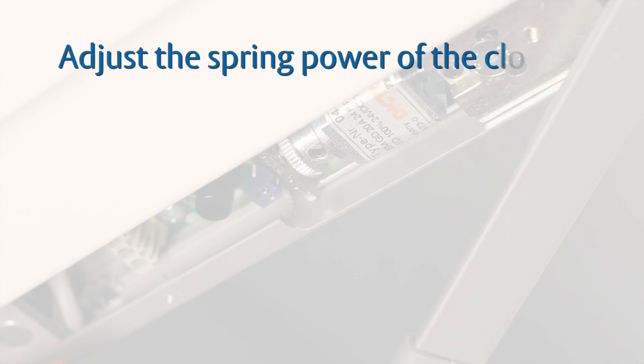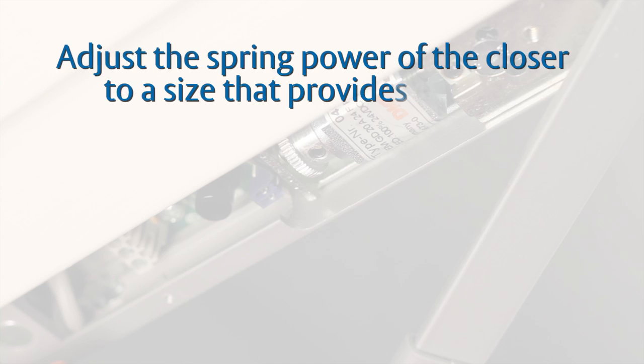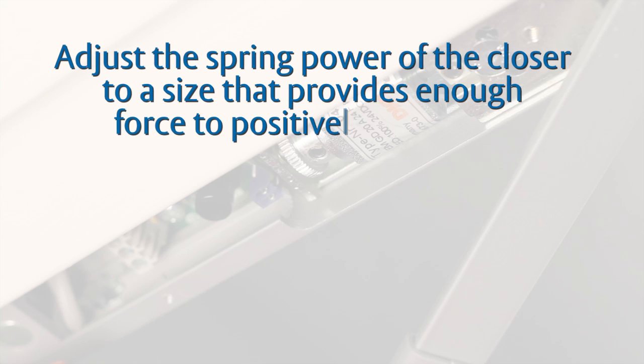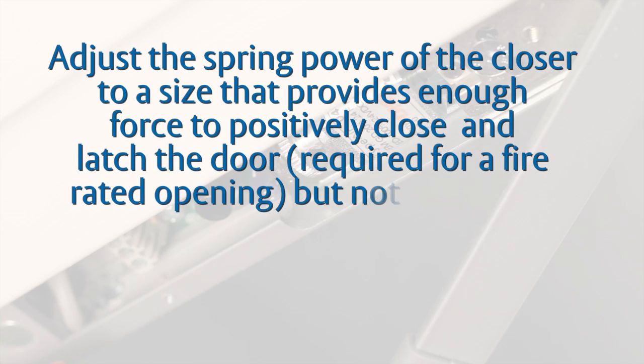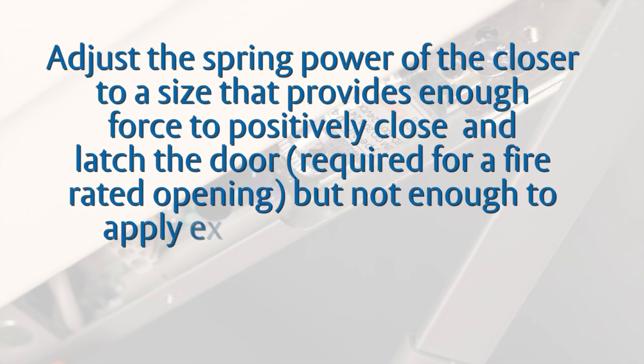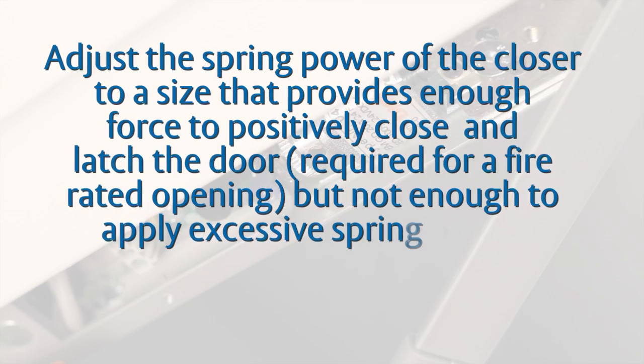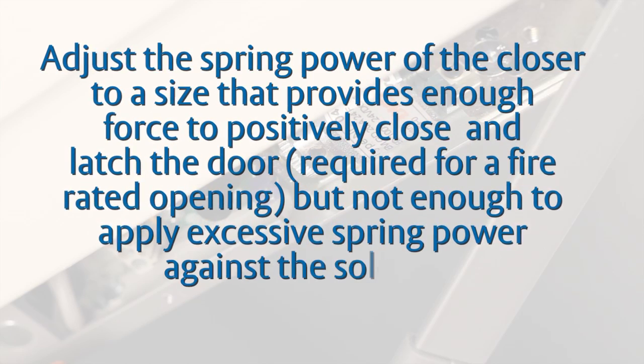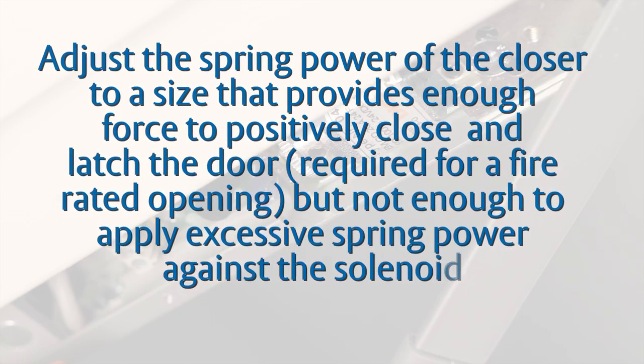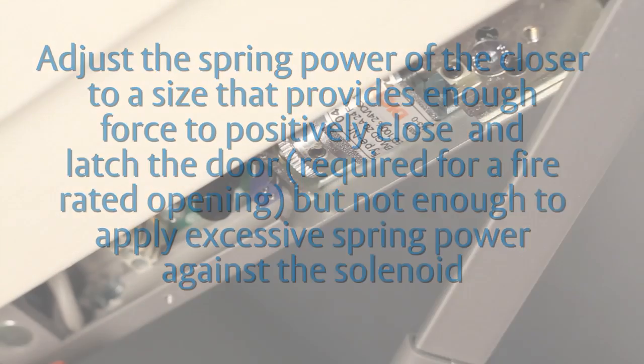With that in mind, adjust the spring power of the closer to a size that provides enough force to positively close and latch the door, required for a fire rated opening, but not enough to apply excessive spring power against the solenoid.